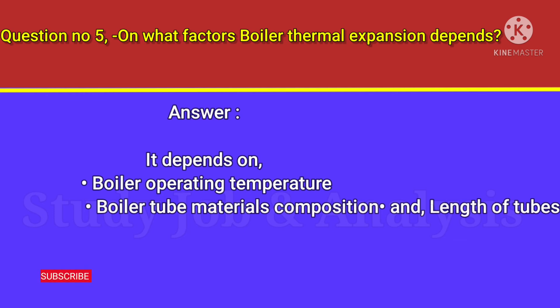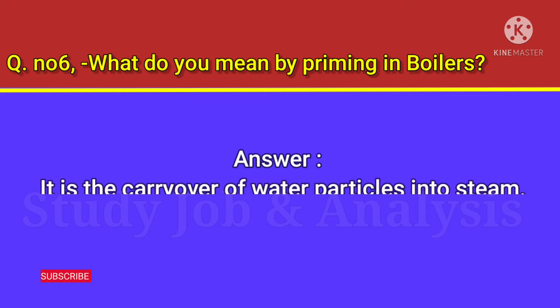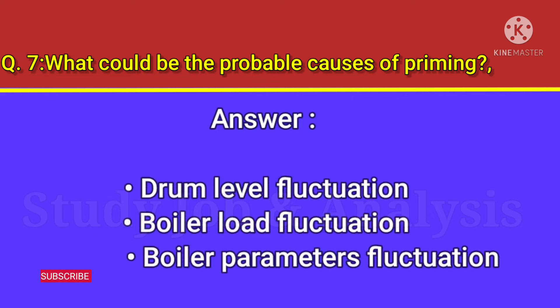Question number six: what do you mean by priming in boilers? Answer: It is the carryover of water particles into steam. Question number seven: what are the probable causes of priming? Answer: Drum level fluctuation, boiler load fluctuation, and boiler parameters fluctuation.